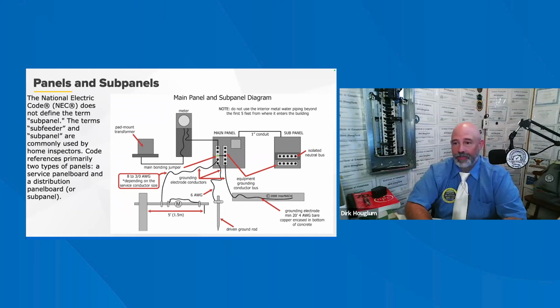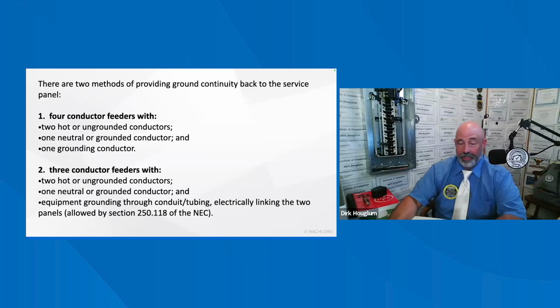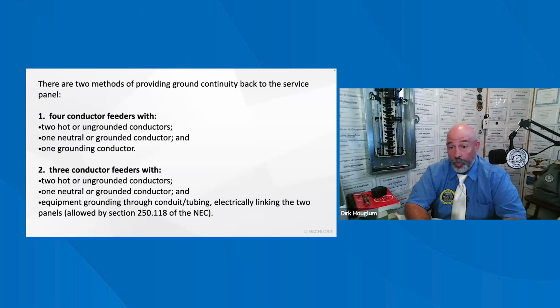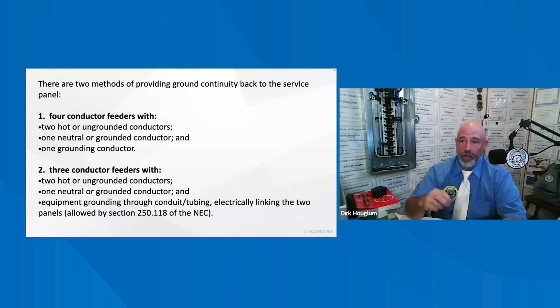So according to the 2008 NEC, this is not allowed in new construction. So in all cases, a 4-wire feed to the detached structure is required in order to isolate the grounded conductor and the equipment grounding conductors. There are 2 different types of feeders, 4 and 3 conductors. Each is allowed in the code book under 250.118. Article 250 in the NEC is all about grounding and bonding. So when in doubt, the best way is to check the codes in that section for reference.